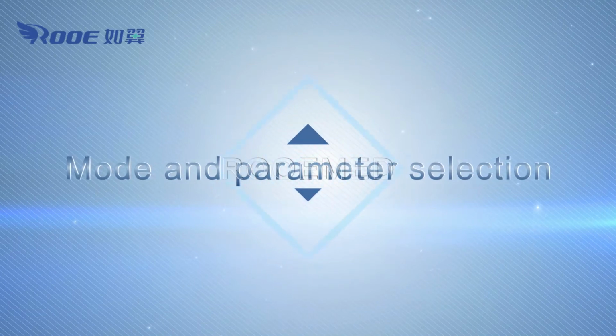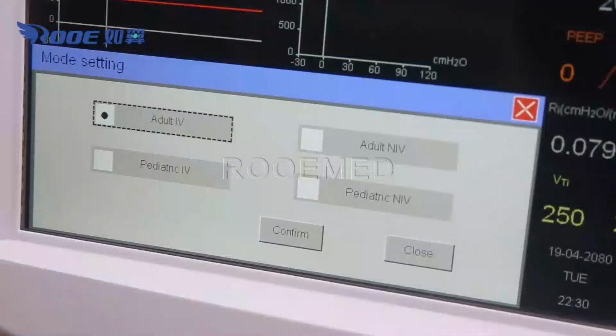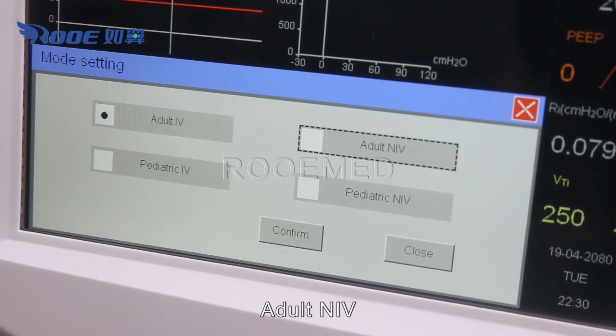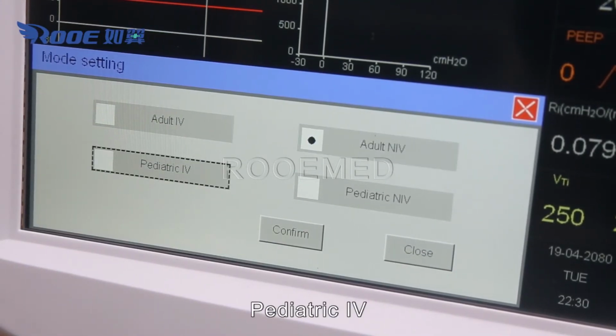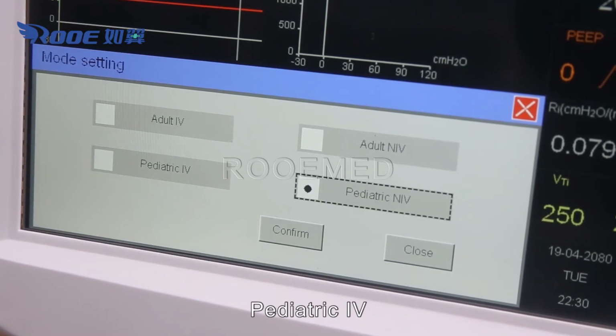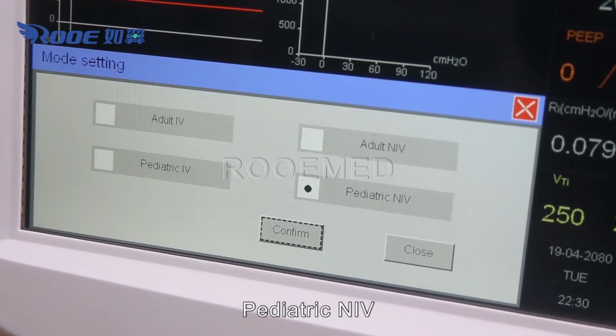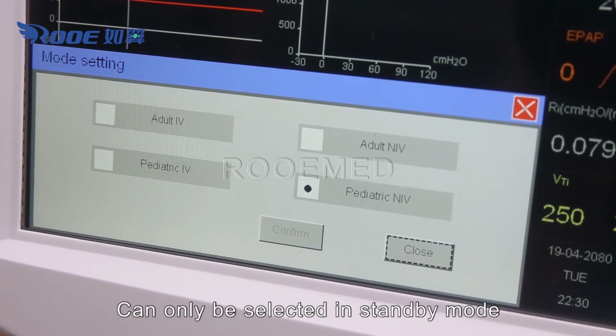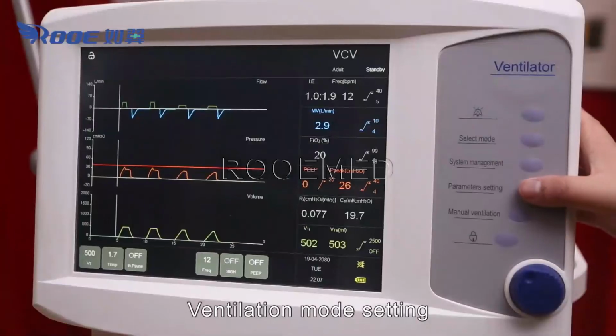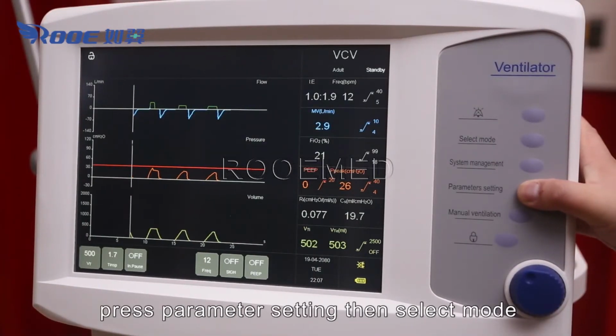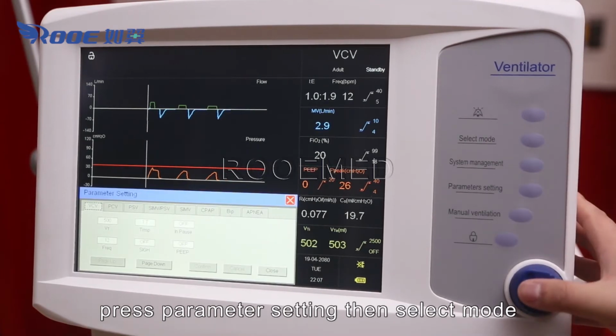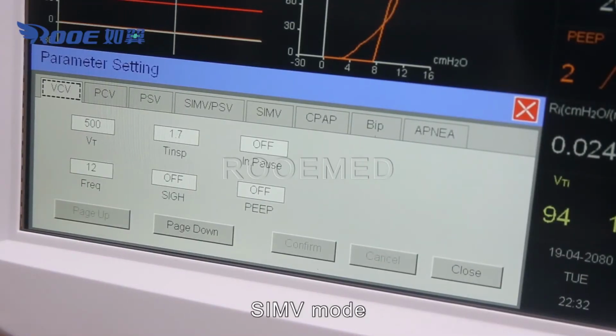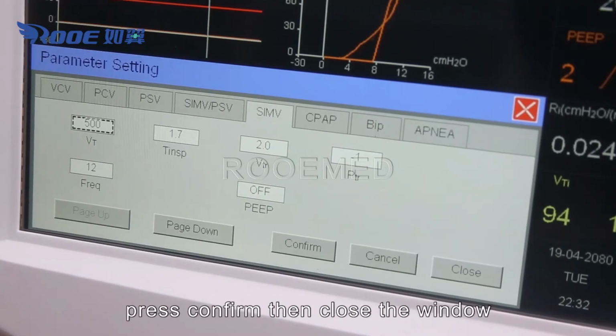Mode and parameter selection. Mode selection: Adult IV, Adult NIV, Pediatric IV, Pediatric NIV. These can only be selected in standby mode. Ventilation mode setting: press parameter setting, then select mode. For example, SIMV mode. Adjust knob. Press confirm, then close the window.